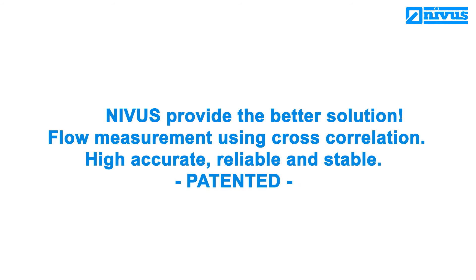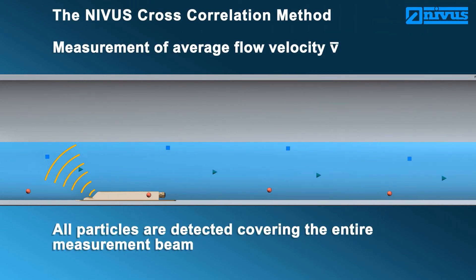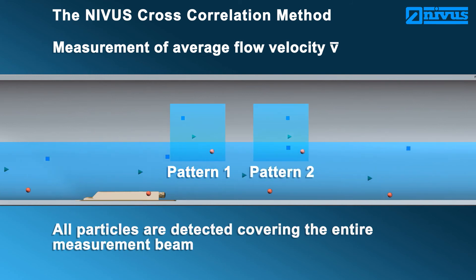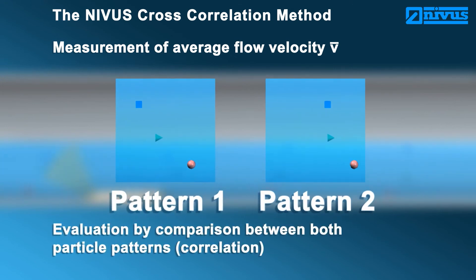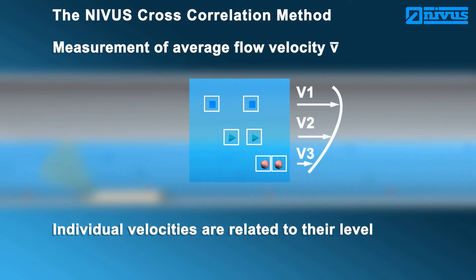NIVUS provides the better solution: flow measurement using cross-correlation — high, accurate, reliable, and stable. The NIVUS cross-correlation method is not a spot velocity measurement. Here, all particles are detected at the same time, covering the entire measurement beam. The particle images are evaluated by comparing correlation to each other, and this comparison repeats within a few milliseconds. In addition to the individual particle velocities, the relation to the flow level is available. Due to this, it is possible to represent the flow profile directly.